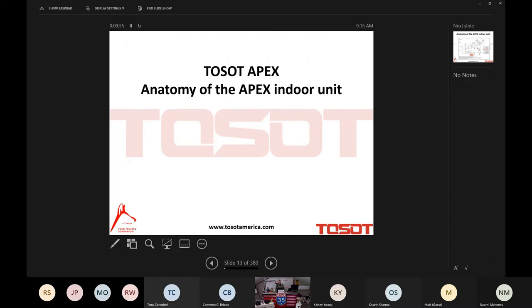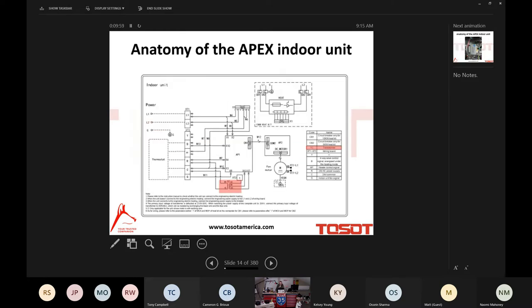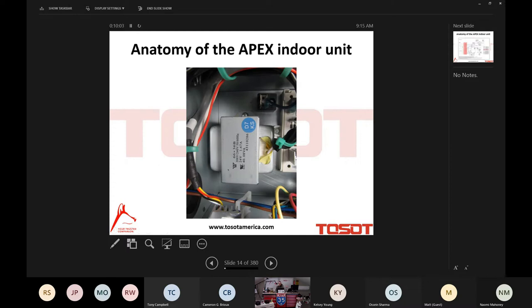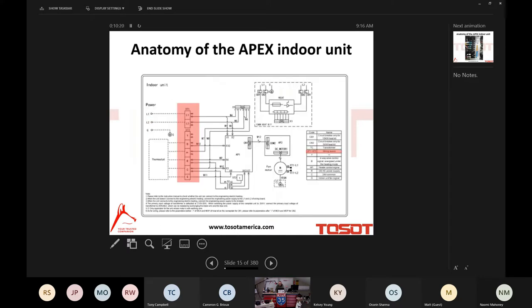We're going to go through the anatomy of the Apex. We'll start with the indoor unit. And guys, we'll start with the transformer. There is a 208/230 to 24-volt transformer because the Apex system, unlike our mini-split systems, does utilize a 24-volt control system. So that's why that transformer is internal to the electrical box of the Apex indoor unit.